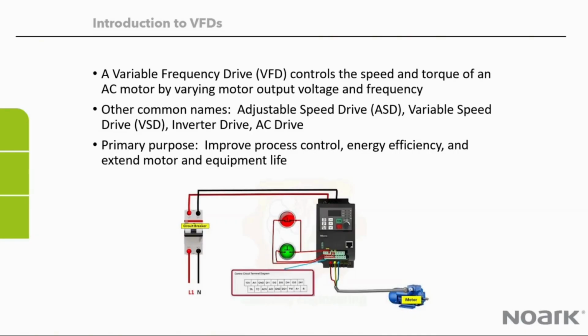A variable frequency drive, also known as a VFD, controls the speed and torque of an AC motor by varying motor output voltage and frequency. Some of you may have heard of a VFD also as adjustable speed drive, ASD, variable speed drive, VSD, sometimes the word frequency is put in there, inverter drive, or AC drive. All common names that are used in the industry. The primary purpose is to improve process control.